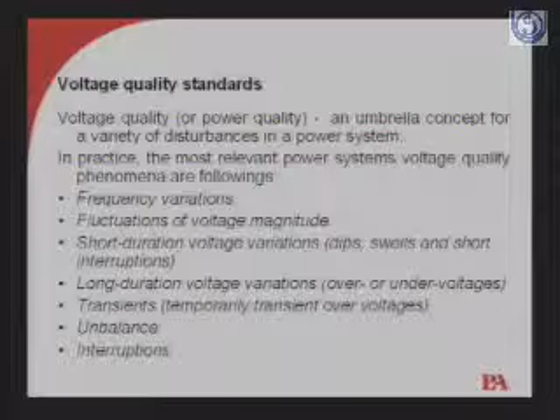So here we can see, as it appears on your screen, the importance of voltage quality. It has a growing economic impact on the customer and the network operators. The cost associated with lack of quality can be large, especially for industrial consumers, as we have discussed. Voltage quality is considered at the customer's connection point and is closely related to the customer's equipment. Some important examples: customer equipment contains more microprocessor controls and power electronic devices, which can be sensitive to variations in voltage quality, as I gave you the example of the motor. The growing importance of higher energy efficiency has led to an increase in the number of adjustable motor drives and shunt capacitors, which generate harmonics on the power system.